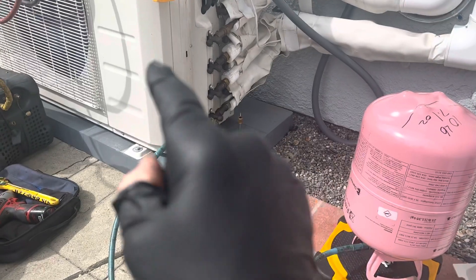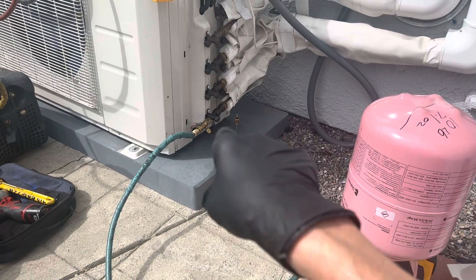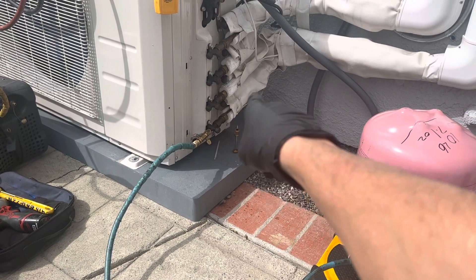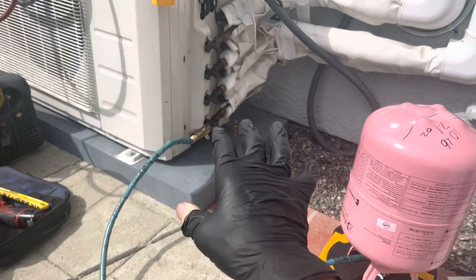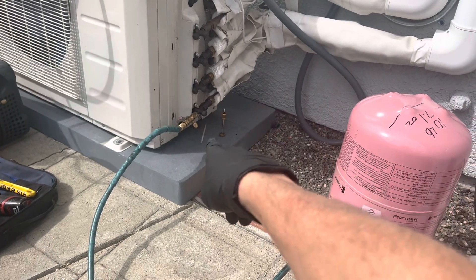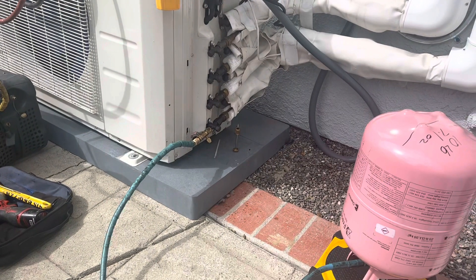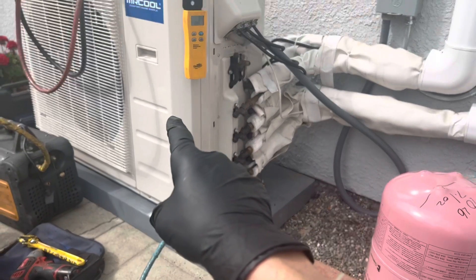There is a mini split that will fool you that isn't variable displacement — it's a straight up one speed. There are some manufacturers who will trick you, because on mini splits you have a cold line and a cold line and suction on both sides. That messes a lot of guys up because they think it's like regular residential split systems, where you have a liquid line that's hot liquid gas and then a suction gas line. That is not how most mini splits work. There are some that have single speed compressors with the expansion device inside and do have a liquid line, but they look like a regular mini split.